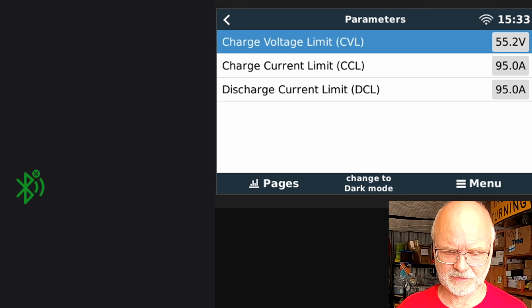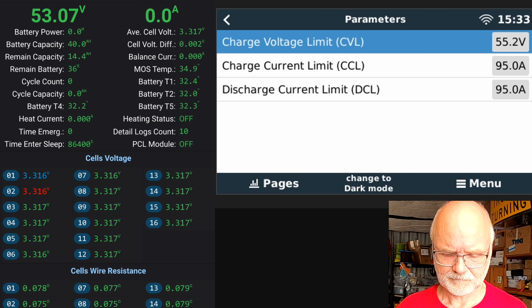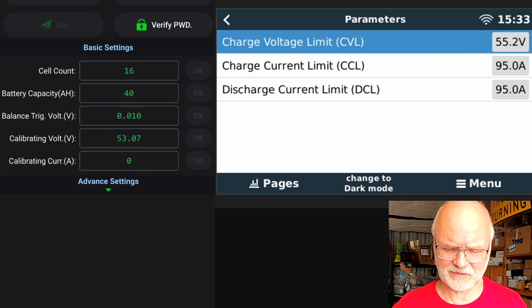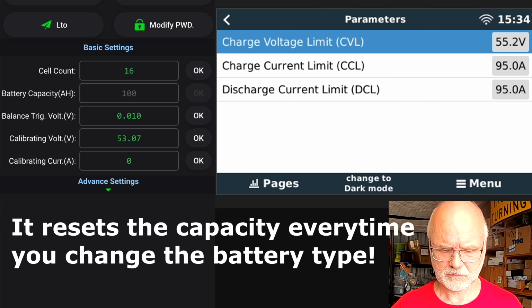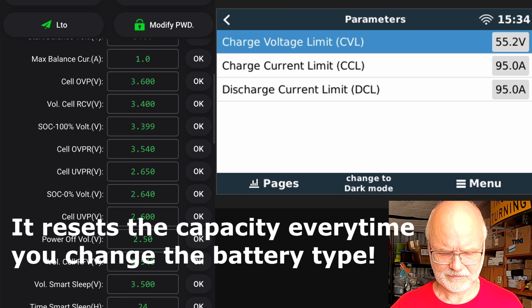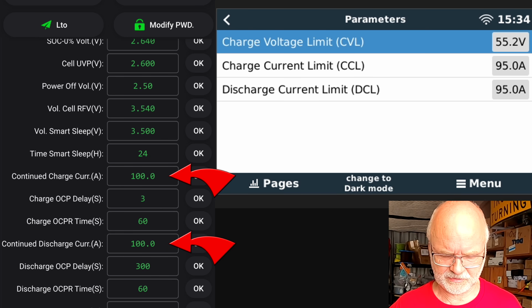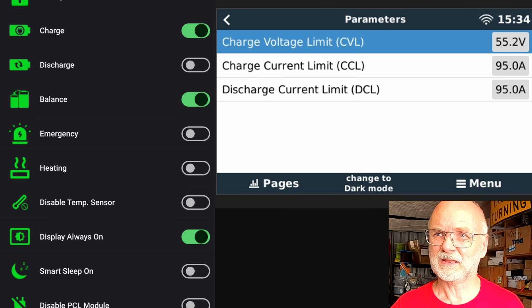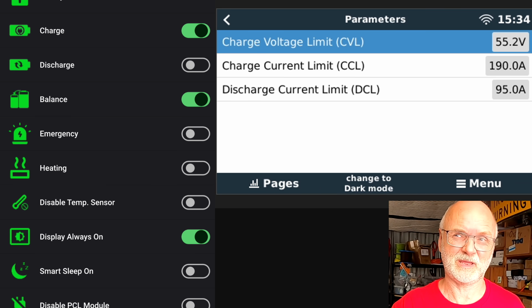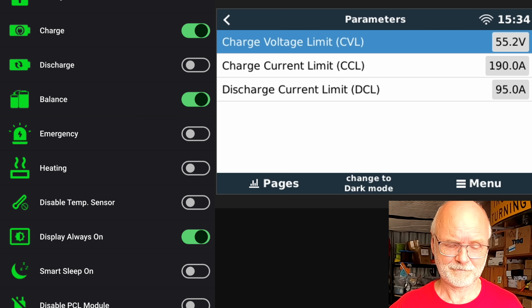Okay, let's go into the slave battery. What? This one sits on 40 ampere hours again as well. 100 ampere hour. Oh, really, guys? Okay, continue charge current 100, discharge current 100. Go into here, turn on charge, and see what the CCL does. It should go to 190. It doesn't? Go on. Ah, here it comes. Okay, perfect. 100 amps for each of the BMSs makes 200, and they take 5% away. Just so if you have any spikes in your current, it doesn't trigger the protection. And we turn on discharge as well, which should show 190 as well then. Great. Okay, so this all works.